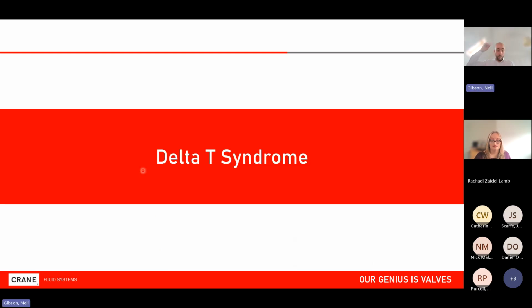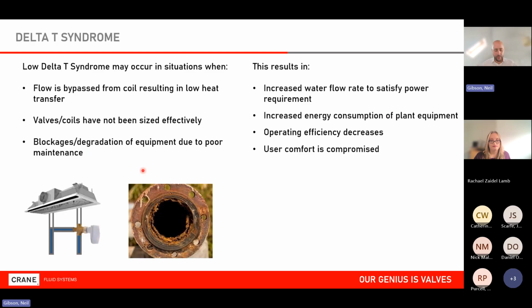So getting on, so building more intelligence into the system. What we also have is more issues as well. So delta T syndrome is a major one. I'll give a recent example of one which we came across. We're up at a university, quite a large estate. In fact, they have multiple estates, all running off heat networks. And they were showing the system, the live BMS feed. And going into the building was 80 degrees Celsius for the heating system, and coming out was 78. So a horrific delta T issue.